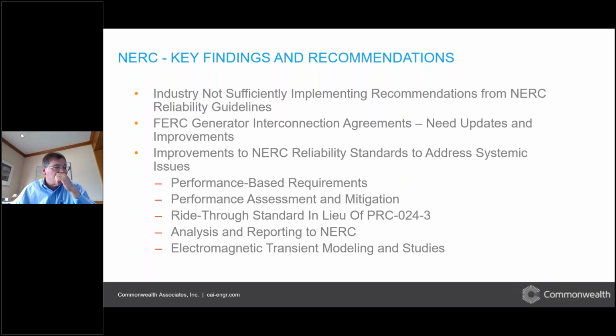So that's probably going to be something you'll see coming out of NERC: you have to prove it. Along with that, the performance assessment and mitigation: if you have an incident, prove that you've corrected it and taken proactive correction. There's most likely going to be a change with the ride-through standard in lieu of PRC-24. Then analysis and reporting to NERC: a lot happens that doesn't get reported to NERC, so expect more coming from that.